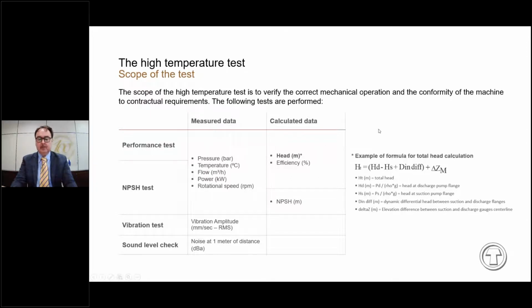My presentation will be a brief introduction to the scope of a high temperature test. Usually, pump performance tests are executed at ambient temperature, and the results are then corrected to the design temperature using mathematical formulas. TMP is anyway able to perform the performance test at a higher temperature than the ambient, as we will demonstrate later on, in order to match the design temperature. The scope of the high temperature test is to check the correct mechanical operation of a pump at the design temperature, and also to verify the conformity of the machine to the contractual requirements.